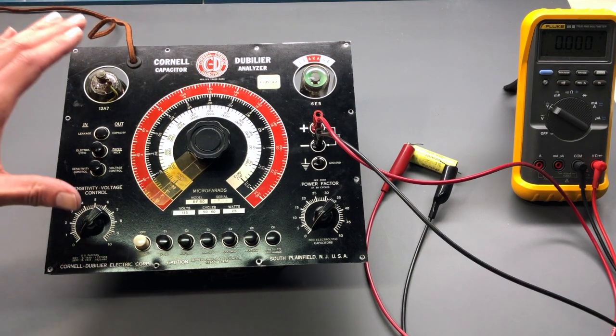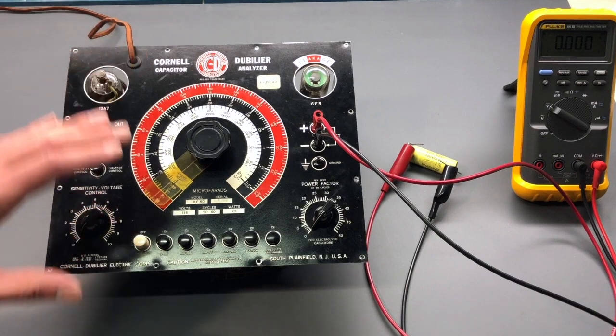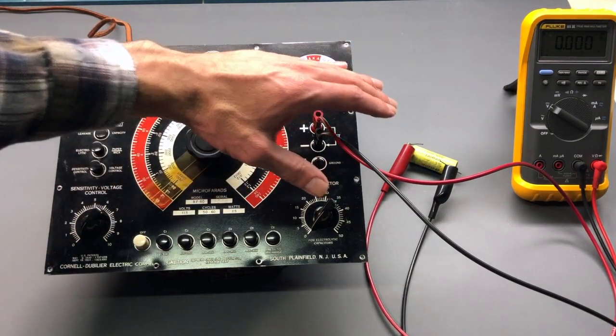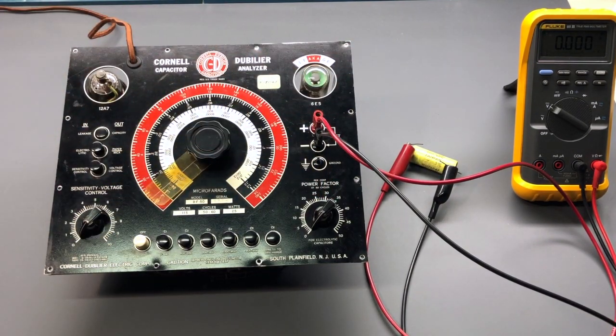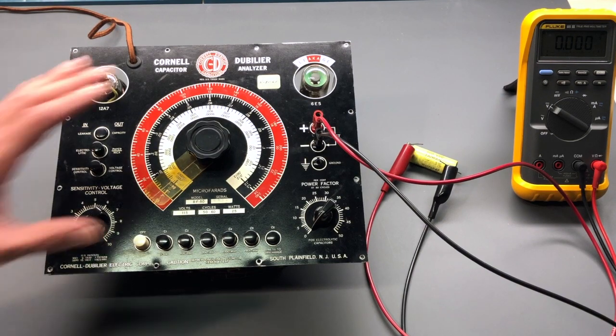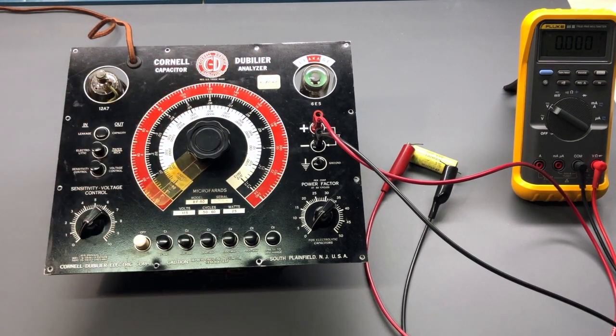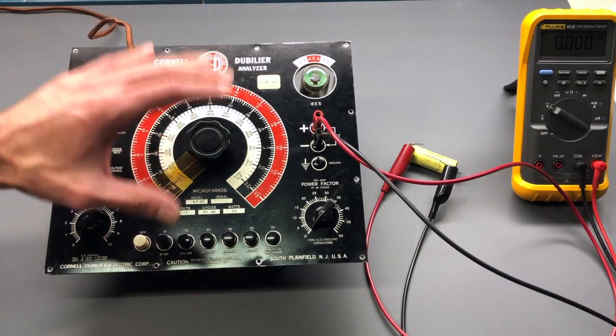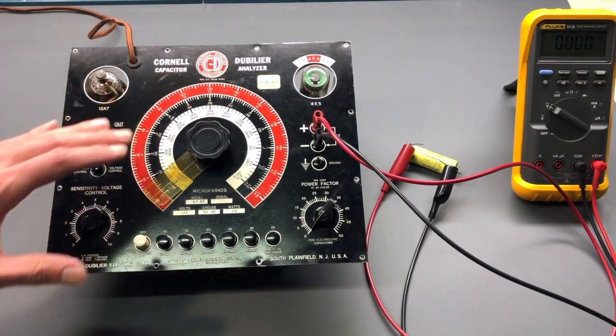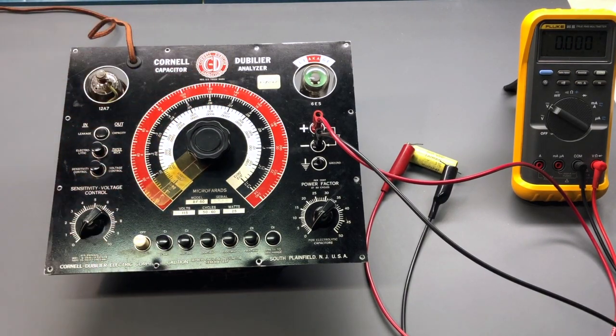With using testers like this, you want to be very careful of the voltage that's applied to the capacitor, because certainly you could damage a capacitor if it was not rated appropriately, and a capacitor that you might find in a modern circuit that was, say, 25 volts or something like that could easily be damaged on a tester like this, because it just was simply not made to test low voltage capacitors. This is really for capacitors in the 200, 300, 400, 500 volt ranges that were very typical back in the day when this was made.